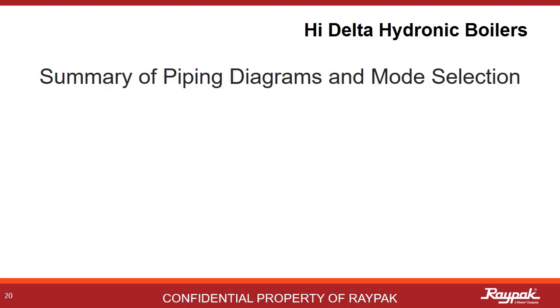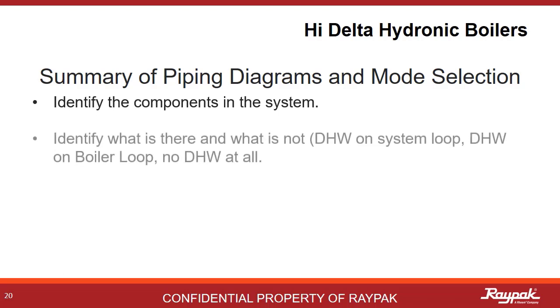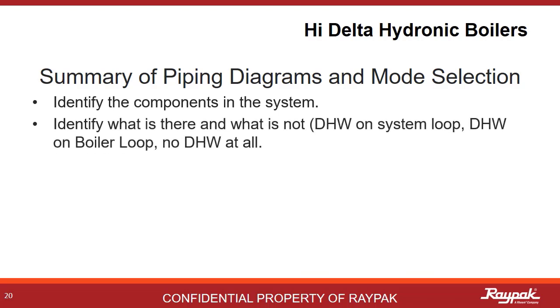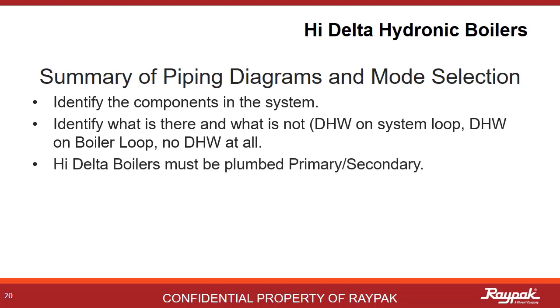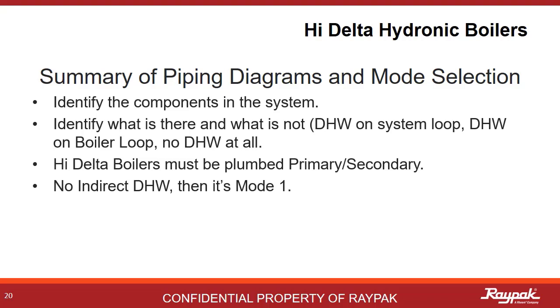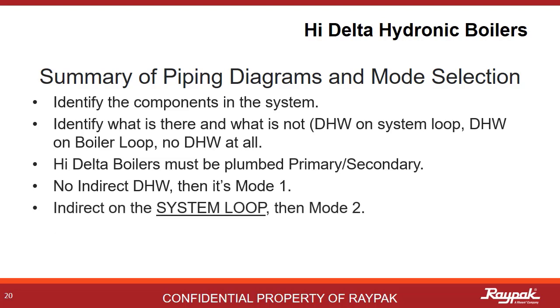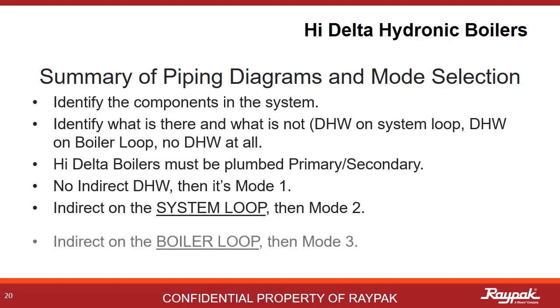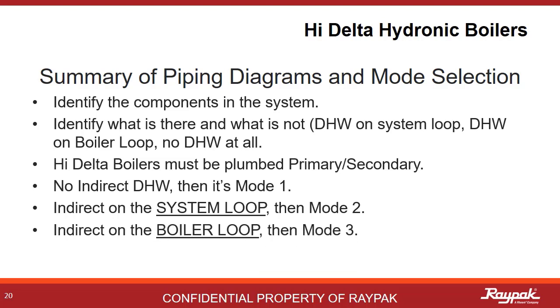Here are some overall pointers on plumbing systems and how they relate to mode selection for Type H boilers. Identify all of the parts of the system — look for what is there as well as what is not there. Make sure it is plumbed primary-secondary. In most cases, with no indirect domestic hot water present, Mode 1 will be your choice. If you have an indirect domestic hot water present on the system loop, then it's Mode 2. If the indirect domestic hot water is present on the boiler loop, then it's Mode 3.